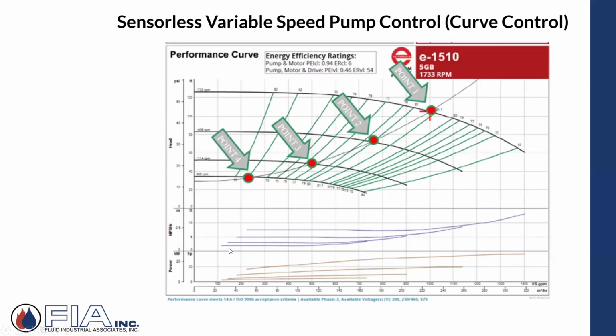It's kind of jumping ahead a little bit, but sometimes when you're doing variable speed, what are you measuring? DP, differential pressure sensors. Some pump manufacturers or some applications for variable speed might be "sensorless," is the term they'll use. And instead of having these differential pressure sensors measuring a difference in pressure between supply and return, they might have some algorithms built into the printed circuit boards, the microprocessor that's on board, and they'll have the pump curve completely mapped out.